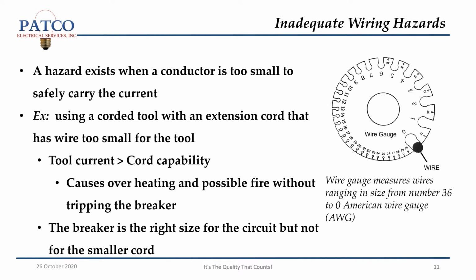Inadequate wiring hazards. A hazard exists when a conductor is too small to safely carry the current. An example is using a corded tool with an extension cord that has wire too small for the tool. Tool current is greater than cord capacity. This causes overheating and possible fire without tripping the breaker. The breaker is the right size for the circuit but not for the smaller cord.